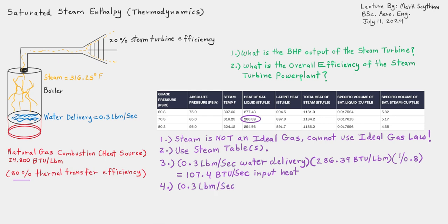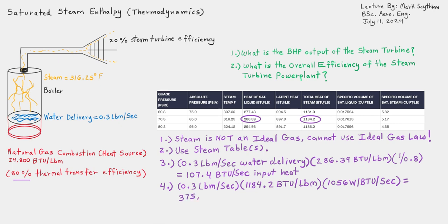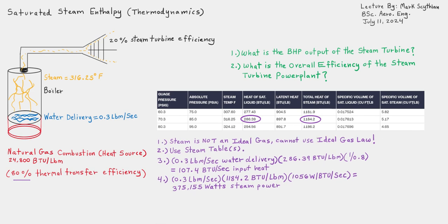Next, we multiply the 0.3 pounds per second water input delivery times the total heat of steam per pound of water — 1184.2 BTUs per pound — then multiply by 1056 watts per 1 BTU per second. The steam power output from the boiler to the steam turbine equals 375,155 watts of steam power.